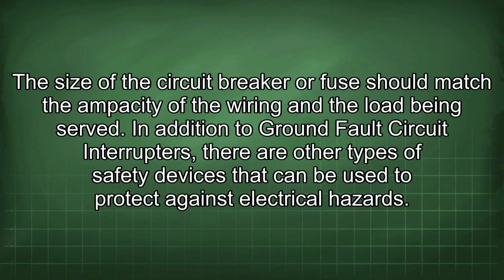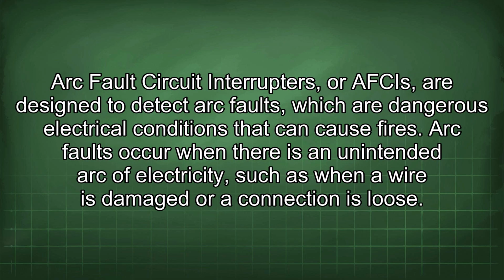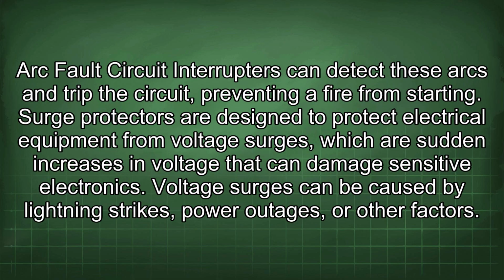In addition to ground fault circuit interrupters, there are other types of safety devices that can be used to protect against electrical hazards. Arc fault circuit interrupters, or AFCIs, are designed to detect arc faults, which are dangerous electrical conditions that can cause fires. Arc faults occur when there is an unintended arc of electricity, such as when a wire is damaged or a connection is loose. Arc fault circuit interrupters can detect these arcs and trip the circuit, preventing a fire from starting.